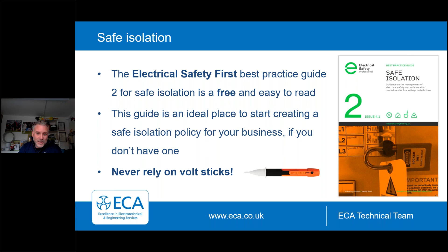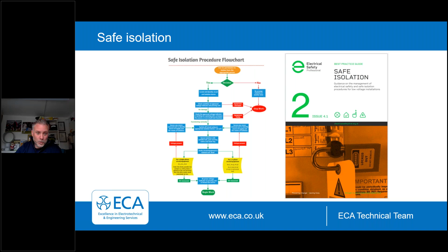Inside that, and we'll come on to that in a moment, there's a safe isolation procedure which you can easily adopt. Typically speaking, I guess this should be in everyone's toolbox: a lock-off kit, a proving device, and the best practice guide too. Never rely on volt sticks. That's one of the most important things to take away from today. They're not a reliable source. So inside Best Practice Guide 2, there's a safe isolation procedure flow chart. Again, this is all free and available from Electrical Safety First, and gives you some more guidance if you want to adopt this or generate your own policy.